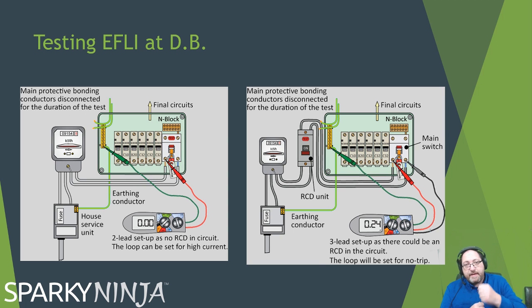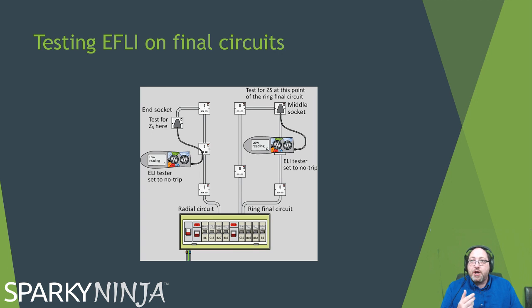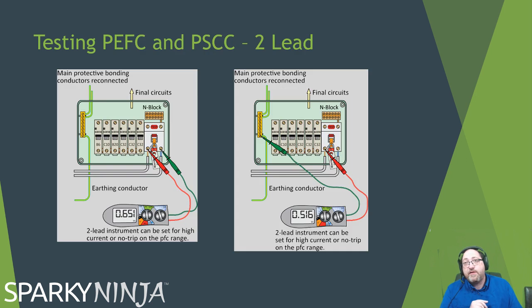So disconnect the main earth and go on that, or, as they've done here, take all the bonding and circuits out and go on the bar with just the main earth in it. If it's a 3 lead instrument, then you just add the neutral to the neutral, and that also will be a live polarity indication, because this will be an energized test. This will be the very first energized test that you do, verifying the earth is there and it's good. Once you've done that, you could go off and do the final circuits. I myself would go on to do the PEFC and PSCC, because I'm at the board.